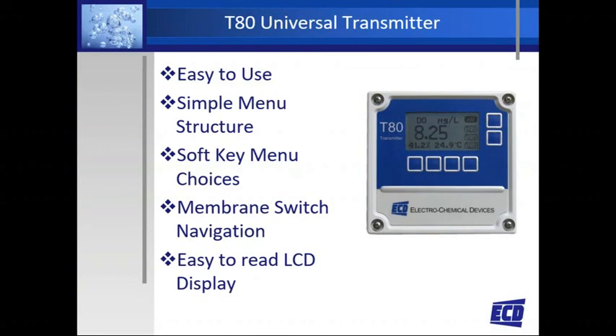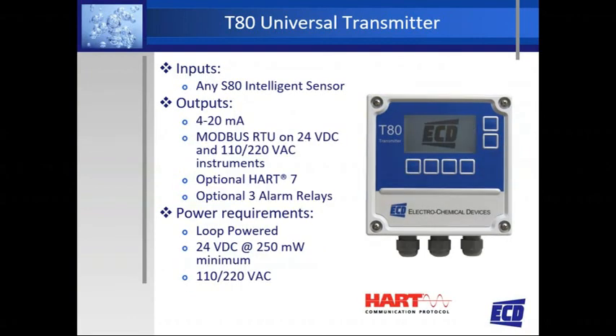It's got a large, easy to read LCD display also. The display shows the process variable, percentage of output, and temperature. If it has relays, it will also show the state of the relays. For the inputs, the T80 transmitter can do up to two sensors, any of the intelligent sensors that we showed on that one screen. For outputs, the standard output is a 4 to 20 milliamp output with Modbus. Optionally, you can get a second 4 to 20 output, you can get HART 7, and there are 3 relay contacts that are also optional.